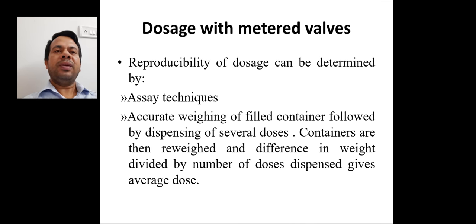Next is dosage with metered valves. Reproducibility of doses can be determined by assay techniques, and a second method is accurate weighing of filled containers followed by dispensing of several doses. In assay techniques, specific amount is taken and can be determined by different analytical procedures. In second method, containers are then reweighed and difference in weight divided by number of doses dispensed gives average dose.